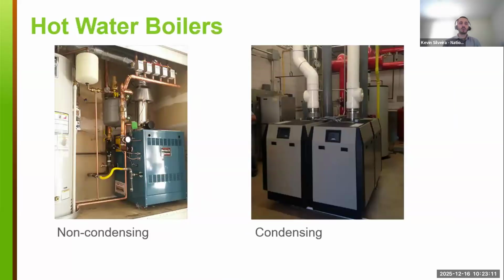That brings us to hot water boilers. There are two types of hot water boilers in a typical building: non-condensing units and condensing units. The way to identify non-condensing boilers is a steel or metal exhaust pipe coming out of the building, versus condensing ones, which typically have PVC exhaust vents for the combustion air. Sometimes in condensing boilers, you'll have a fresh air intake and exhaust system to the boilers.